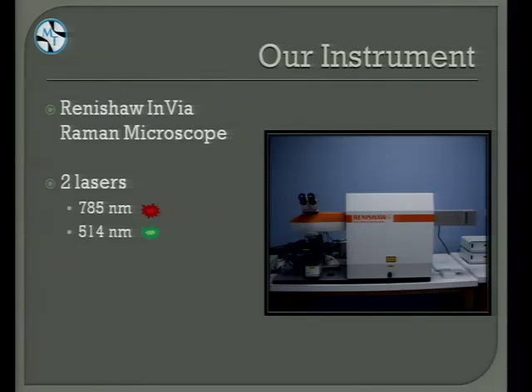A little about our instrument: it's a Renishaw InVia Raman microscope with two different lasers. We have a 785 nm near-IR red laser used for most of our analyses, and also a 514 nm green laser. The reason we have two lasers is to hopefully eliminate possible fluorescence. About 80% to 90% of the pigments we've run have been identified by the 785 laser, and about half of those can be identified with the 514 laser. A nice advantage is we have a dry 100× objective, allowing us to look at very small particles and pigments relatively easily.